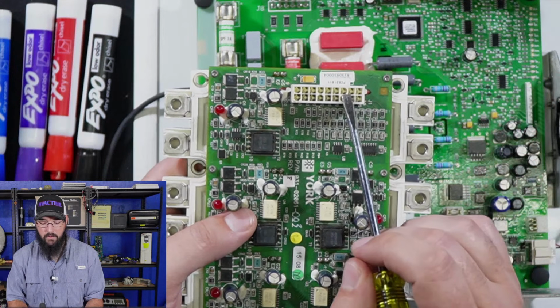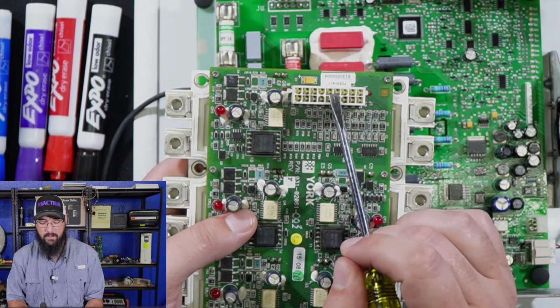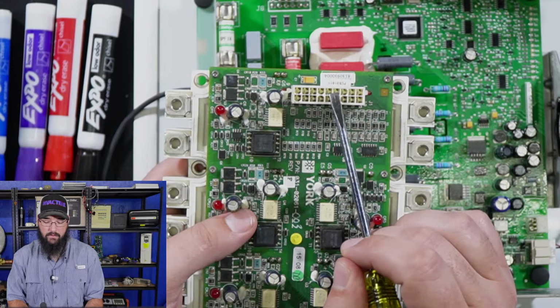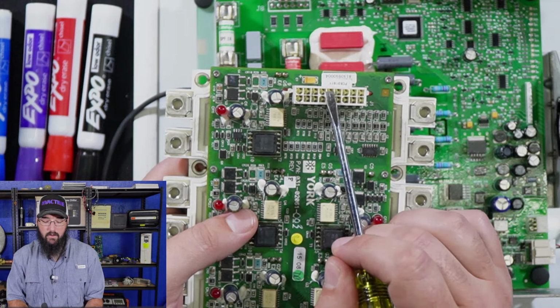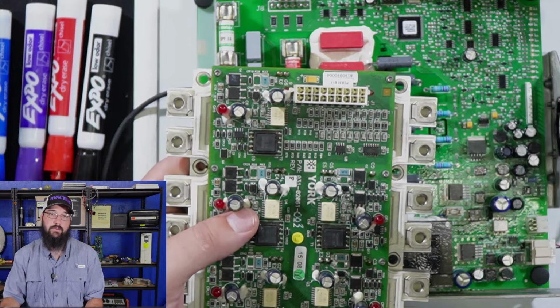So I would then come across and say, okay, this is my J5, and I know that I've got pins 4, 5, 6 right there. These three are my pins going to my transducer. And then I can troubleshoot further from there. I take this approach because whenever I sit down and have conversations with guys about what they're struggling with, this is kind of where they go. Okay, I've got to troubleshoot this component, but I don't really know what to look for. I can't sort out all the wires. And you're trying to trace the transducer wire from the transducer back to the board, which, in some of these panels, is quite literally impossible. You're not going to trace that from one end to the other successfully.